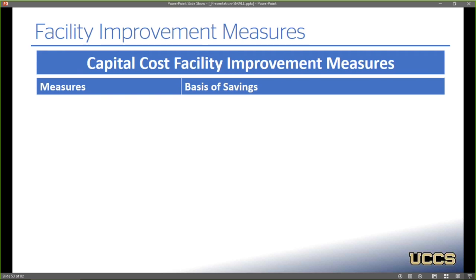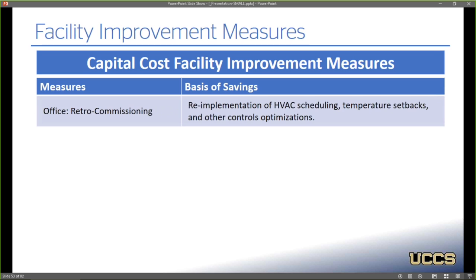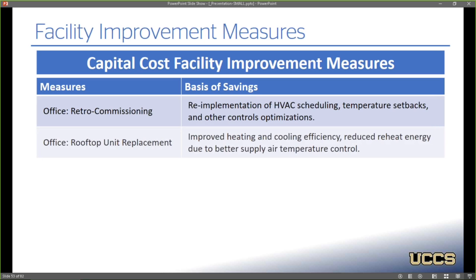On the capital cost improvement measures side, retro-commissioning is top of the list. I feel like if they can identify and repair these issues we're finding, they can re-implement the scheduling and setbacks and other controls optimizations, and that's going to be the biggest bang for their buck. They did mention that they want to replace the rooftop units, and we agree that that's a good recommendation. They will get improved heating and cooling efficiency, as well as having better control of their supply air temperature set point through installing a unit with modulating heating and cooling control. They can reduce their electric reheat energy.